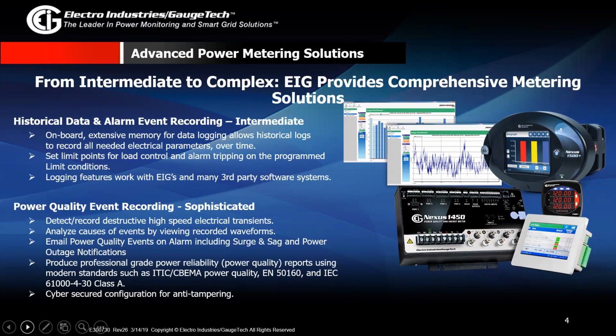You can also get professional grade power reliability reports, which follow the basic standards that more or less everyone uses nowadays: the SEMI power quality graphs, the ITIC curve, and EN 50160 reports. In terms of power quality standards, the meters conform to Class A certification, IEC 61000-4-30 certified. They're also completely cyber secured meters, so this prevents any sort of tampering or hacking into your systems.